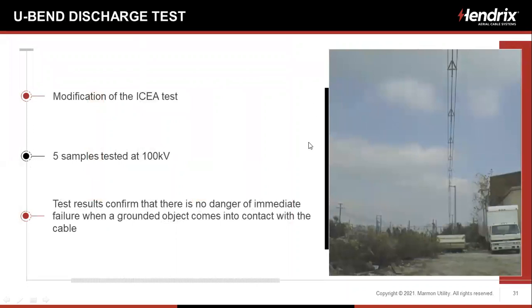Then we did a U-bend discharge test. This was recommended by our consultants. We said it was not relevant. This U-bend discharge test is for underground cable, underground 69 kV cable. We did it anyway. Basically, you bend the cable in a U, you put it down on a steel plate, you energize it at 100 kV, and you go to the time limit. And if it doesn't fail, you've passed the test. So the test results confirm that there's no danger of immediate failure when a grounded object comes into contact with that cable.